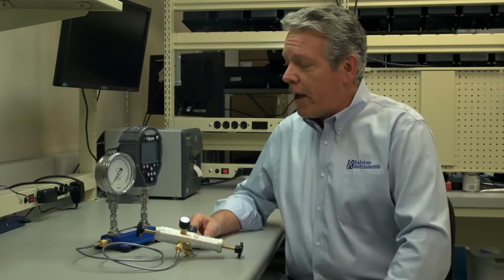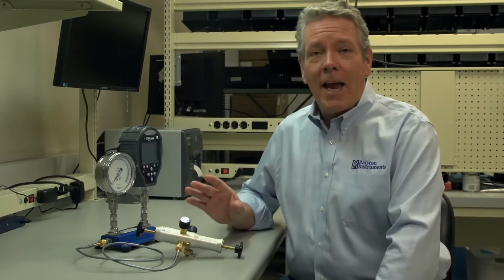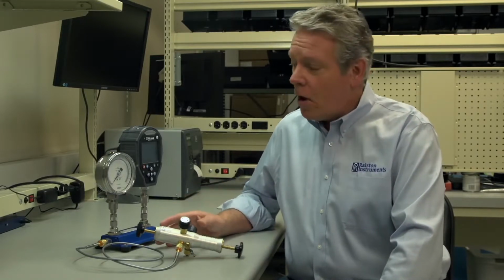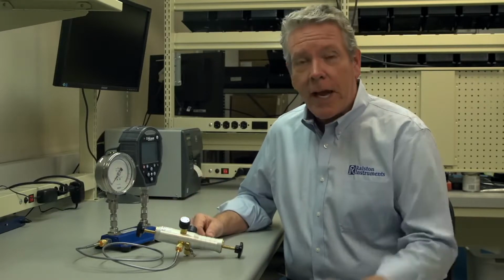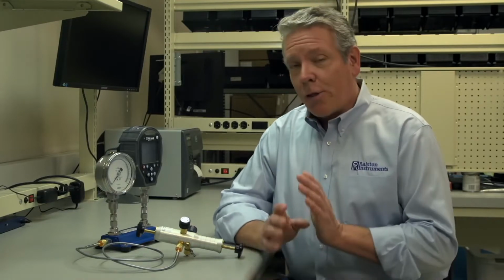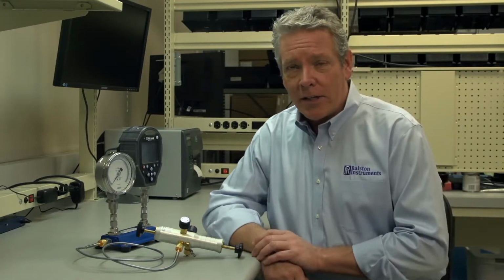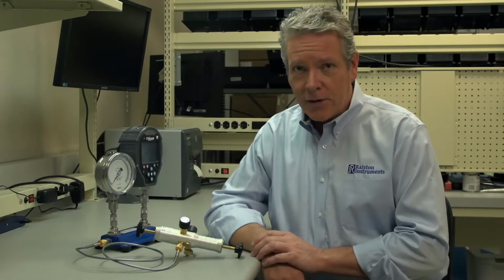Previously, we've used the FieldLab desktop software to create and load the calibration test mode with the appropriate number of test points and permissible error. And be sure to watch our test mode video to see how it's done. Now for this demonstration, we've created a 30 psi calibration test for this specific type of gauge.